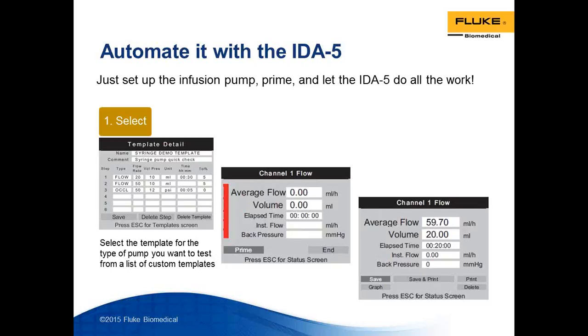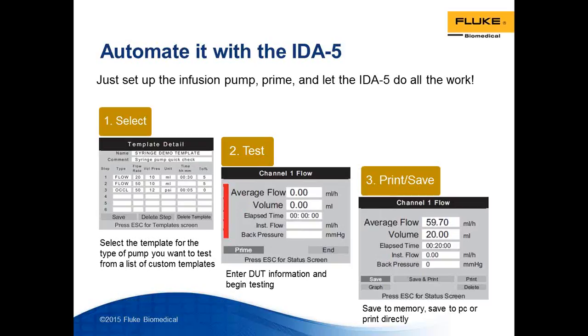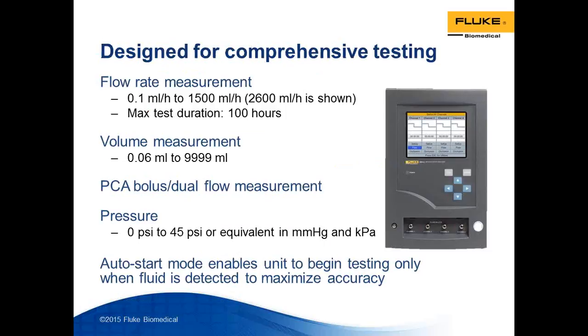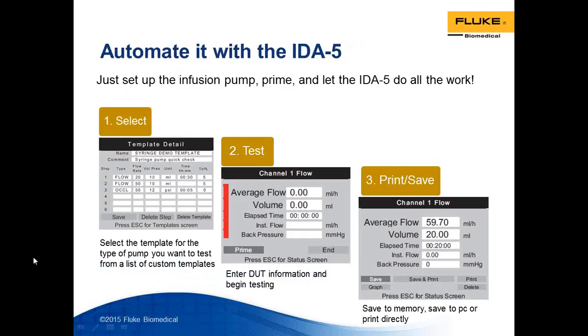This slide depicts how automation essentially works. In the IDA-5, for instance, you select a specified template, you perform the test, and at the end you print and save the data. Here you're seeing that for this particular syringe pump, you have a template stored in the device, which in this case has 2 flow measurements and an occlusion measurement. When you hit next on the template, it performs the testing, and finally it gives you the option of saving the result, saving and printing the result, or printing the graph. A number of options are available to you as far as data and documentation is concerned.